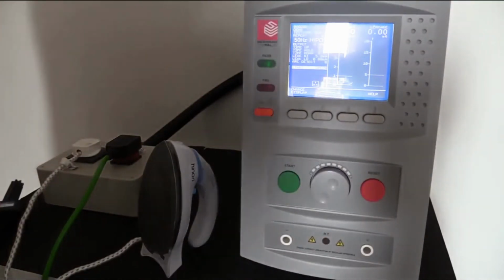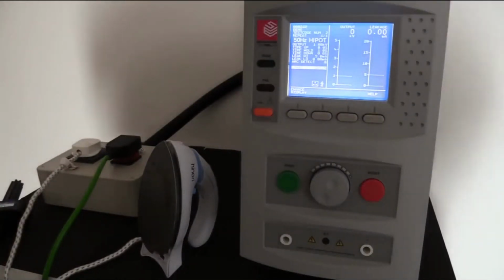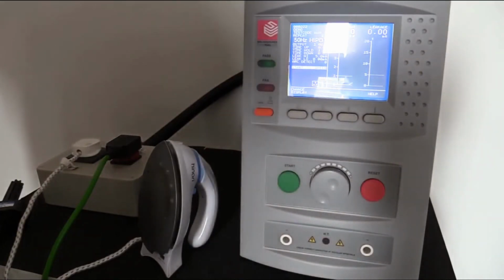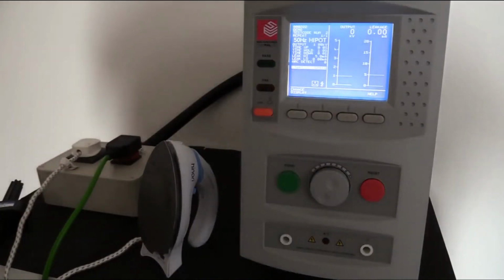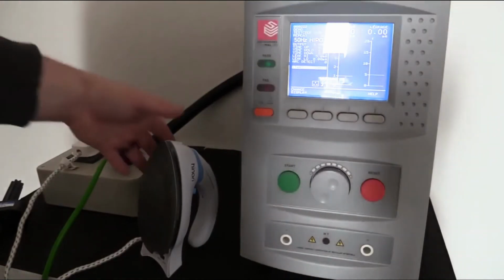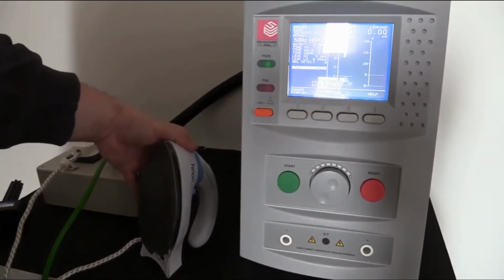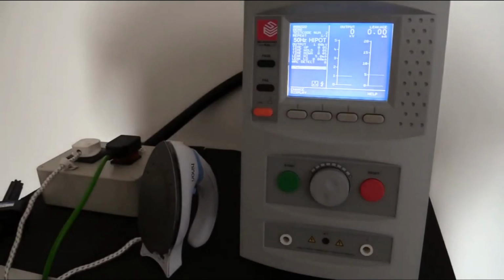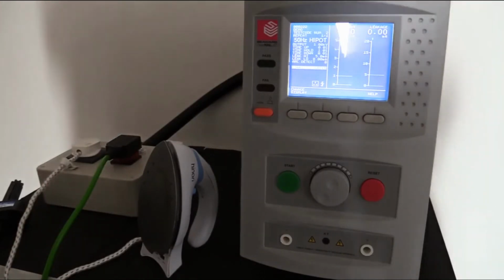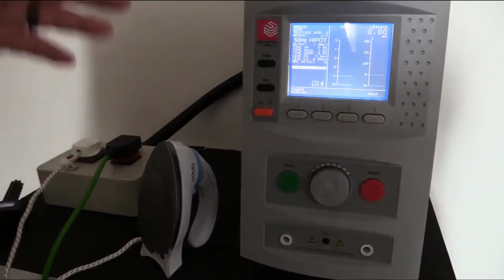Now it's ready to perform the Hipot test. Again, because this is a class 1 product, all the test is performed between the live neutral and the earth cable. So we don't need any probes in this particular instance. We can simply start the test away when we're ready. If your product does have an on-off switch, always ensure it's in the on position. If it has any speed settings, heat settings, it's good practice to make sure they're always generally set to max, and any switches that are on are in the on position. So we're good to go.